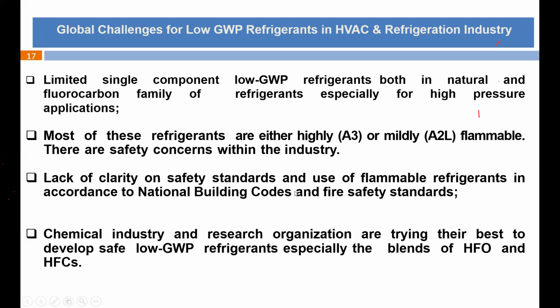Also, worldwide there is a lack of clarity on the safety standards and the use of flammable refrigerants in accordance with building codes and fire safety standards. It is still not very clear which refrigerant to use in complying with the fire safety standard. It is not spelled out in the National Building Code and other laws.